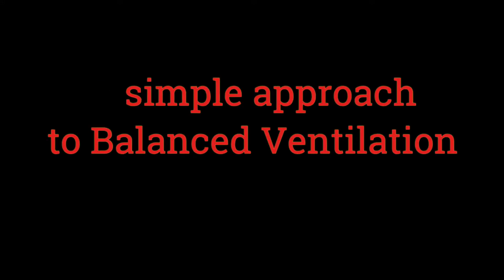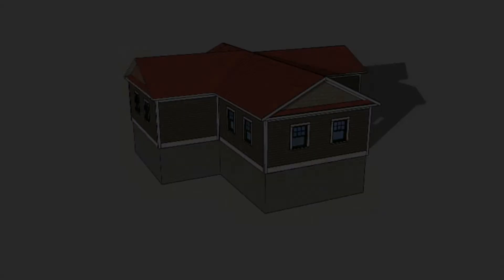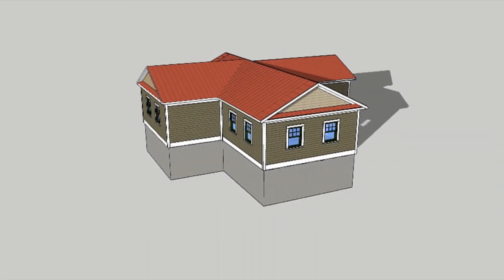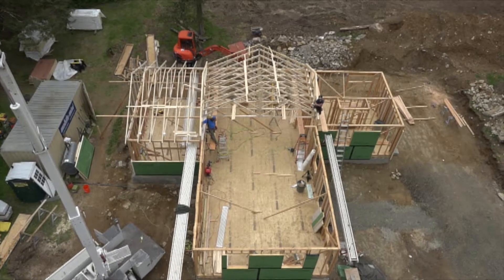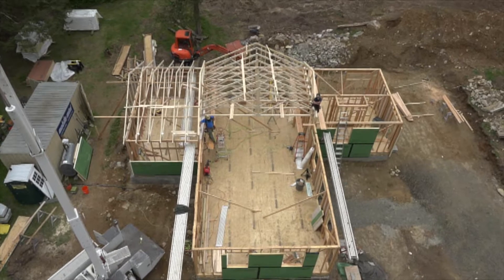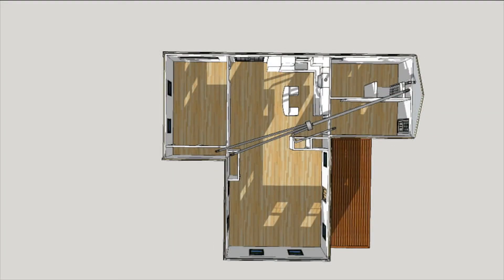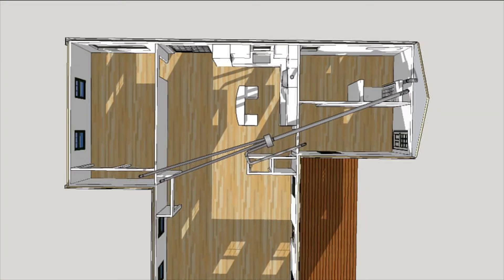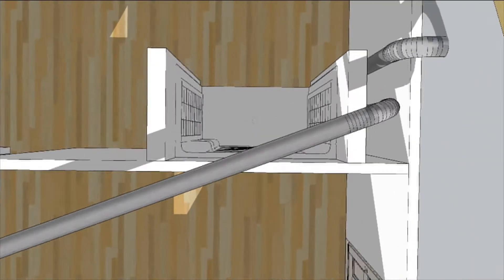Tight little houses need mechanical ventilation to keep the air quality good. In Professional Remodeler's 2017 model remodel, Ben Bogie designed a no-nonsense balanced system based around two 6-inch ducts.